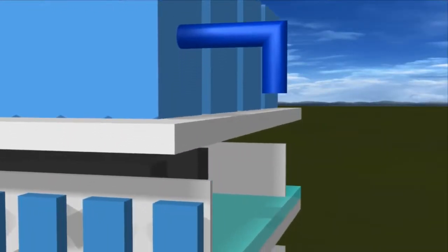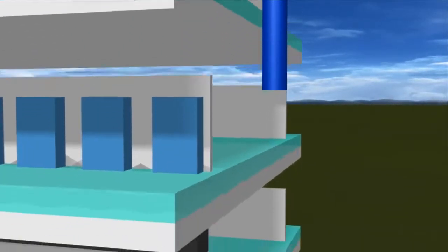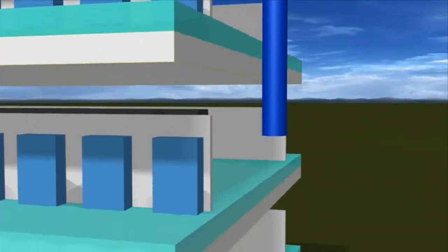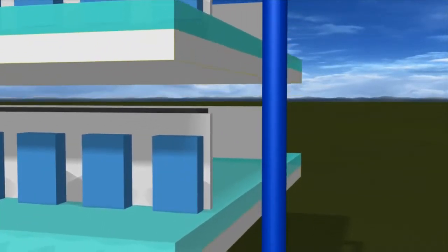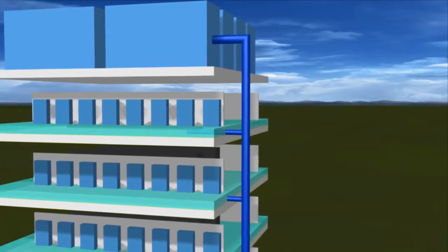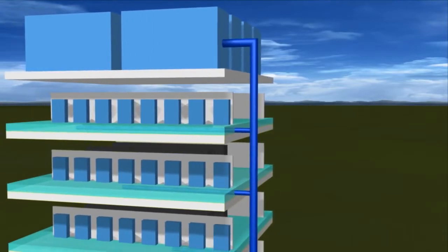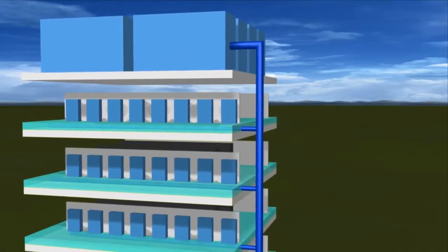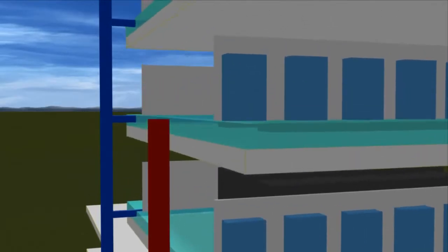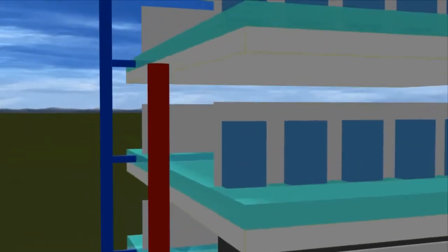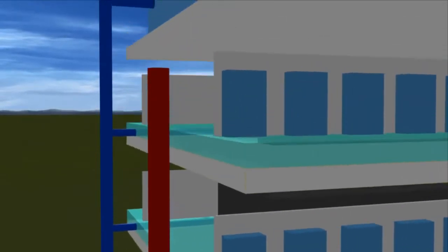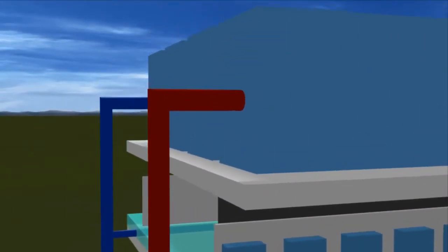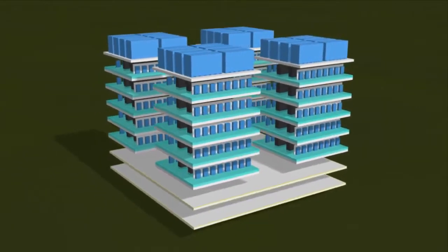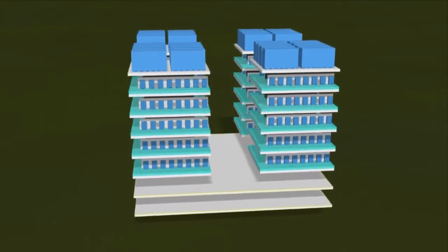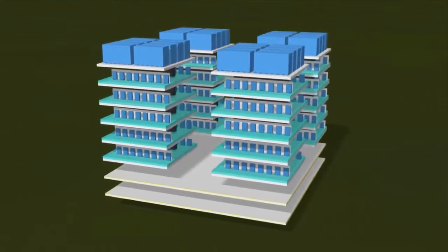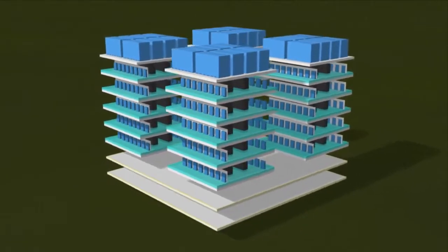Large pipes of 2 feet diameter carry water vertically to and from the chillers in every tower. Within each tower, 1 foot wide pipes are used to deliver water to each floor. The data center uses numerous technologies to improve the power usage effectiveness. Redundancies are built into every aspect of the system, to include piping, chillers, precision air conditioning, etc. Although the medium of cooling is water, the entire system is foolproof with respect to water leakage.